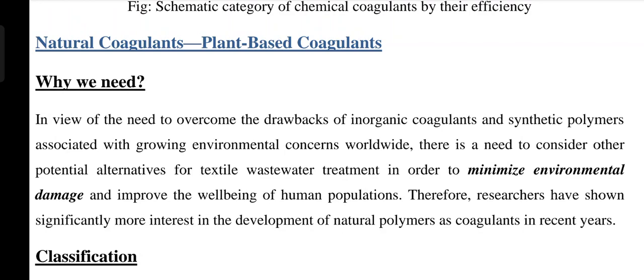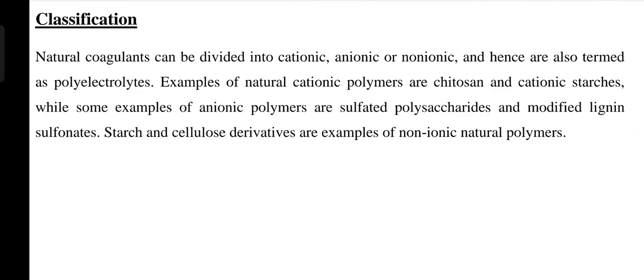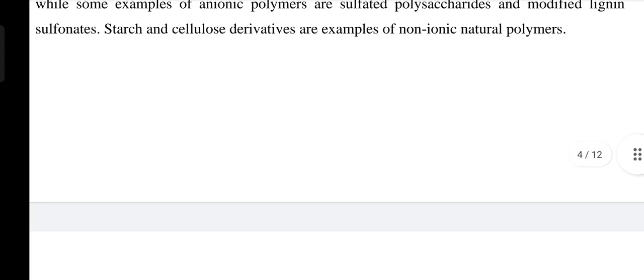Chemicals can damage our environment in various ways, so we use plant-based coagulants rather than chemical coagulants. Classification: similar to chemical coagulants, plant-based coagulants can also be classified into further categories — cationic, anionic, and non-ionic — and are termed polyelectrolytes. Examples of natural cationic polymers are cationic starches, while examples of anionic polymers are sulfated polysaccharides and modified lignin sulfonates. Starch and cellulose derivatives are examples of non-ionic natural polymers, all used as coagulants in wastewater treatment.